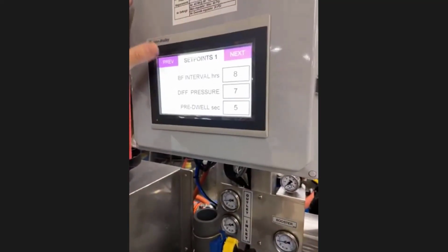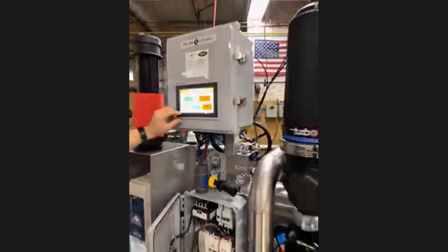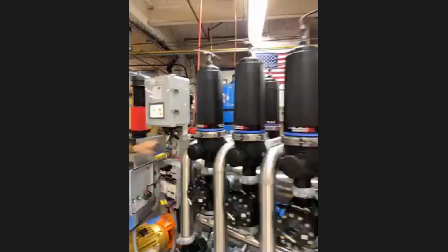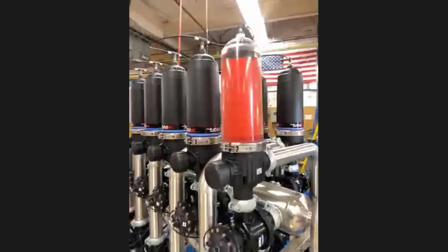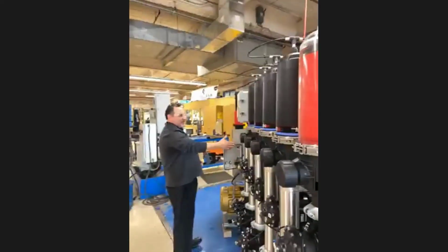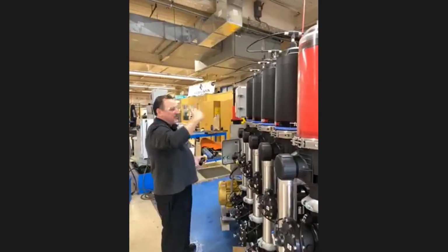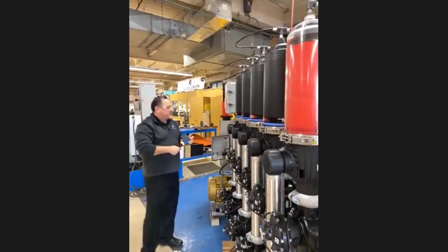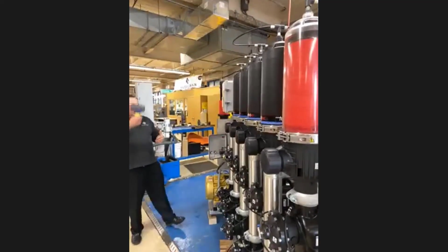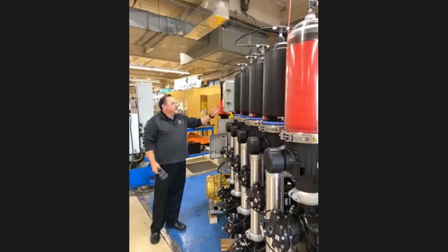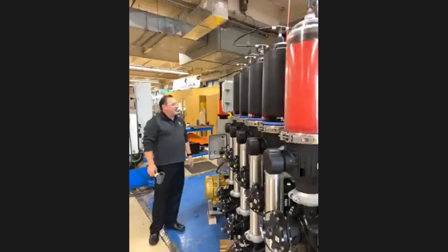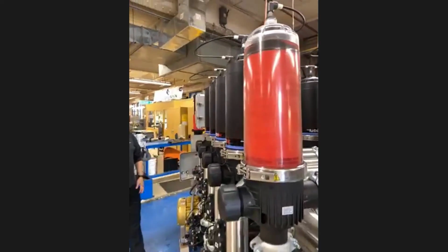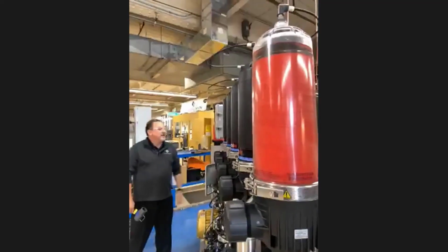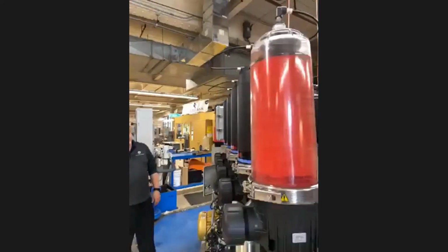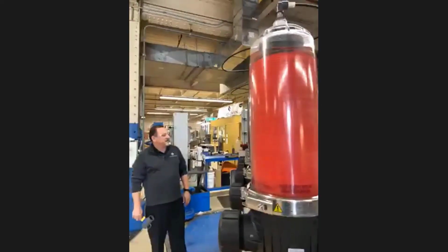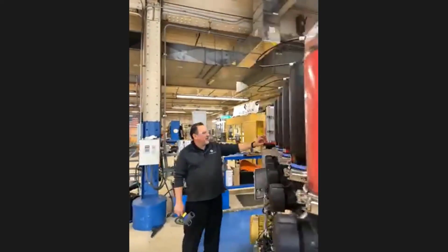And now we'll go through a manual backflush because it's not hitting a differential pressure. So what we're going to do is backflush. And of course, the first 2 pods go first, and then 8 pods are still filtering water downstream. To speed this up, I'm going to fast forward to the last pod after we get it started. So I'm going to go into manual backflush start, which is a button I hit. Now the booster pump is kicking on, and it's going through a backflush one pod at a time. I'm going to fast forward through it.